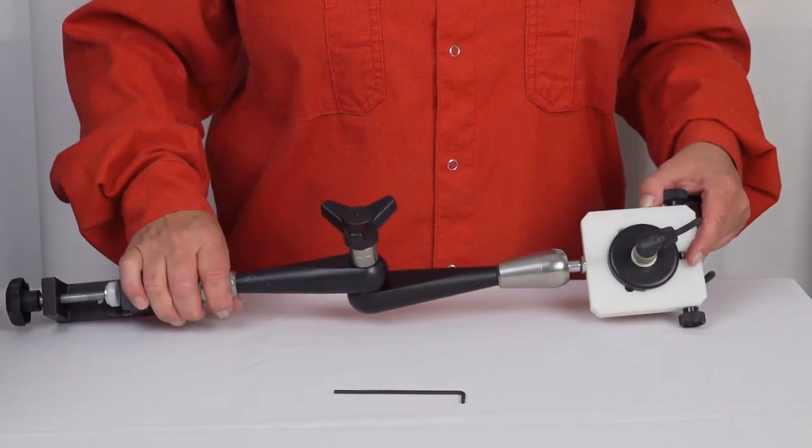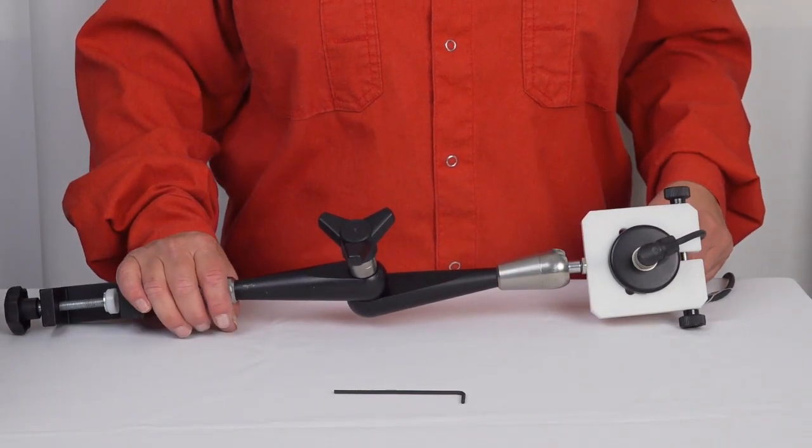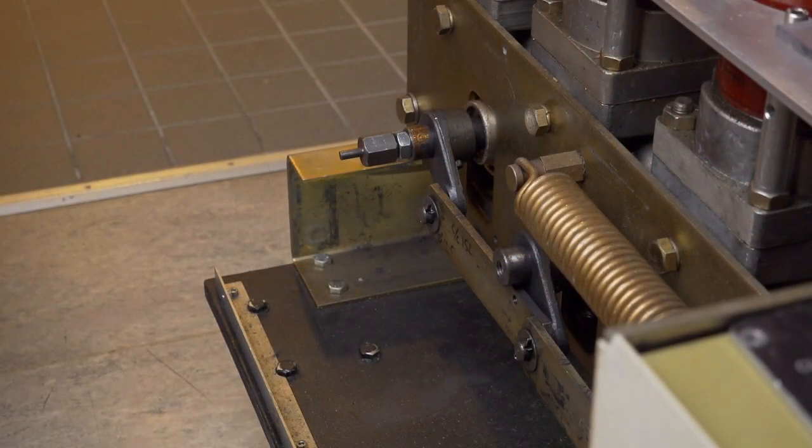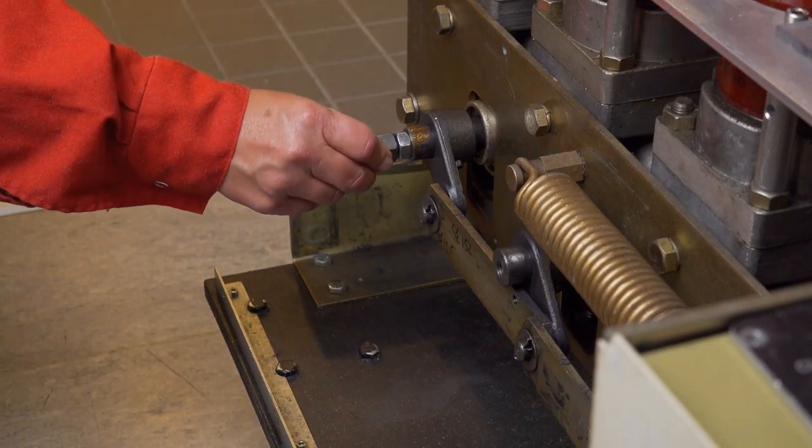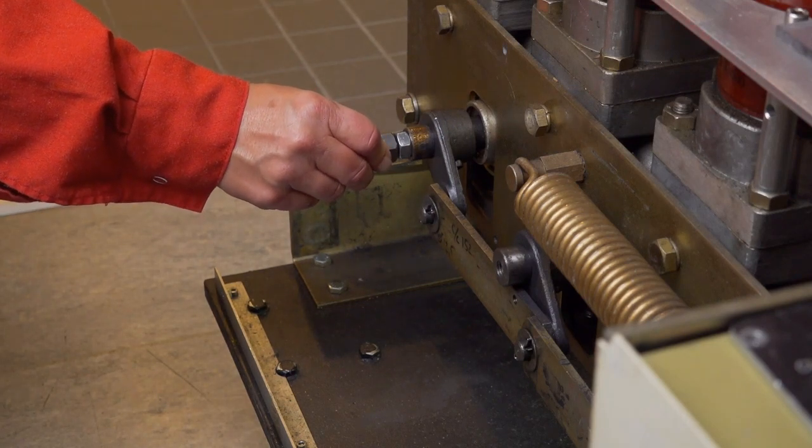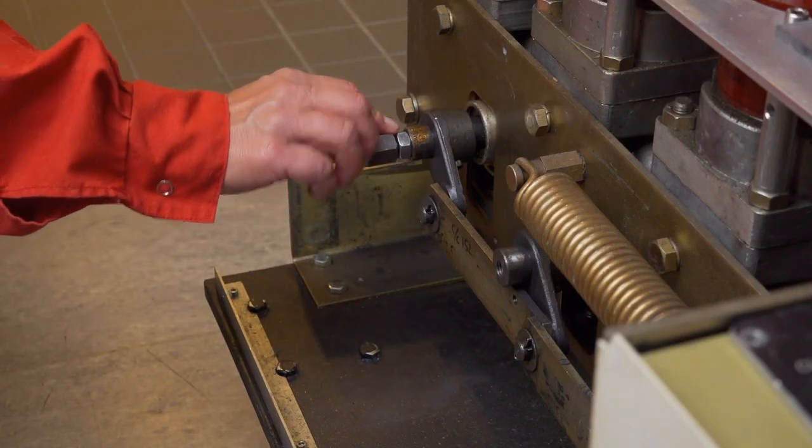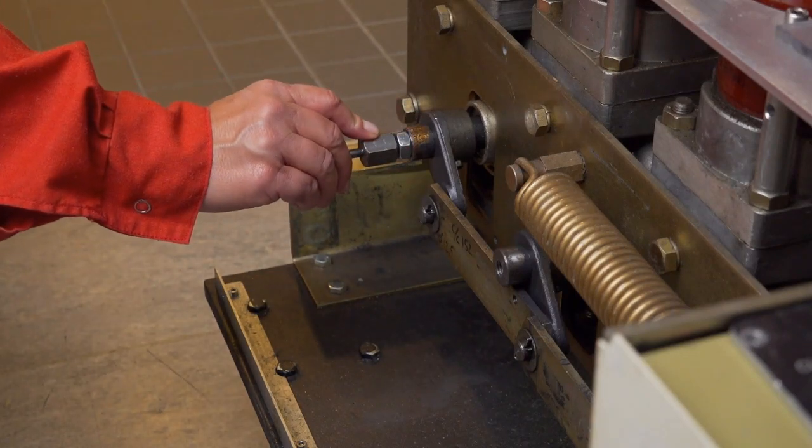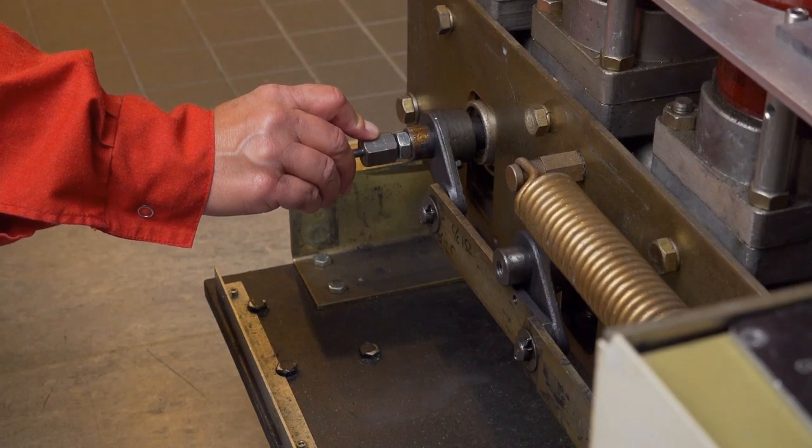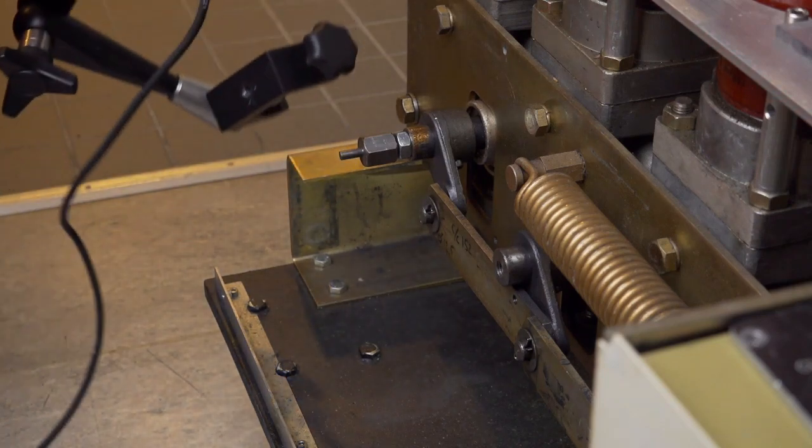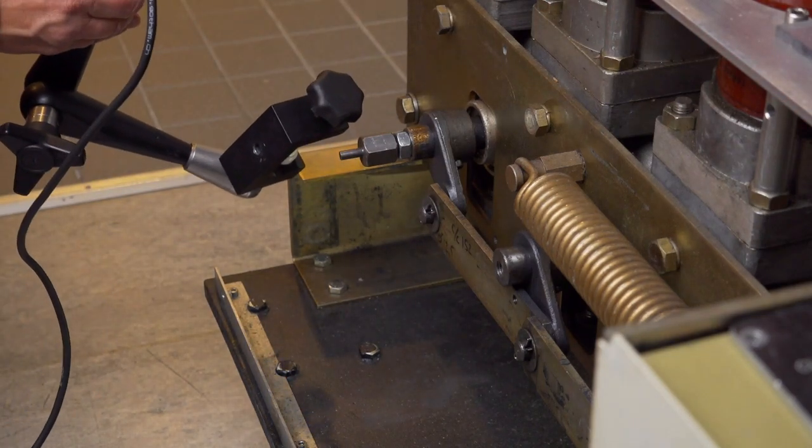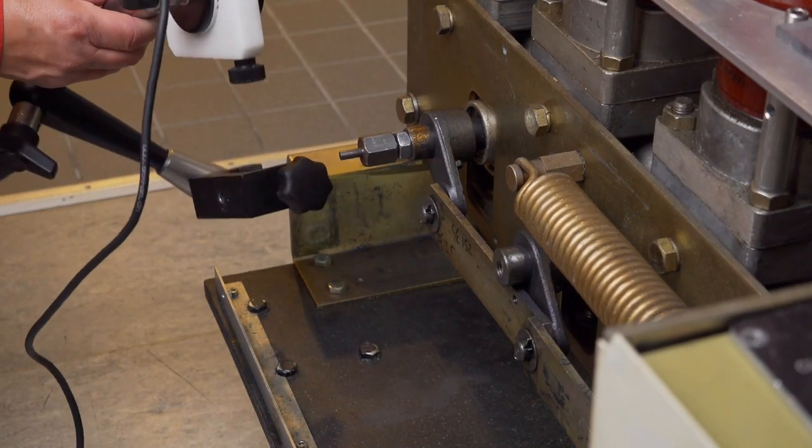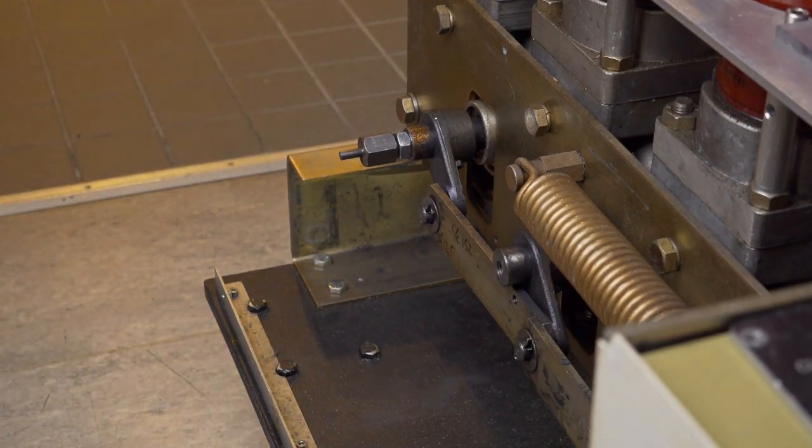And now we are ready to mount it on the circuit breaker. I have connected a part from the rotary kit on a rotating point in the mechanism. This rotating point reflects the motion of a pole. I have prepared the angle so I can easily connect the transducer.